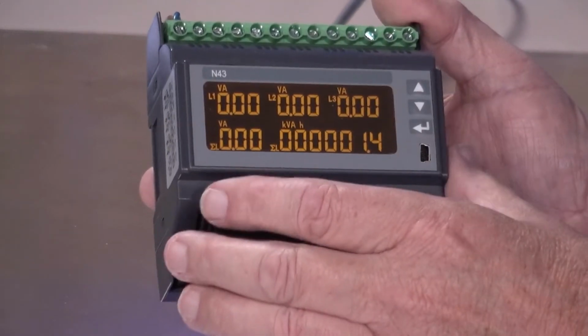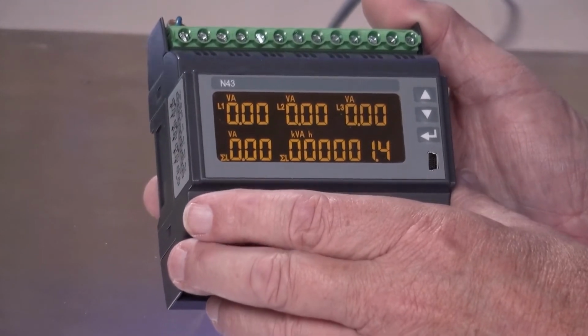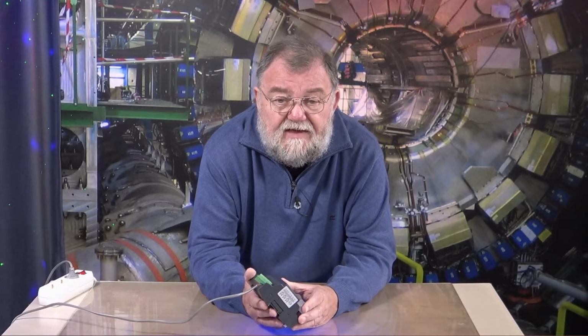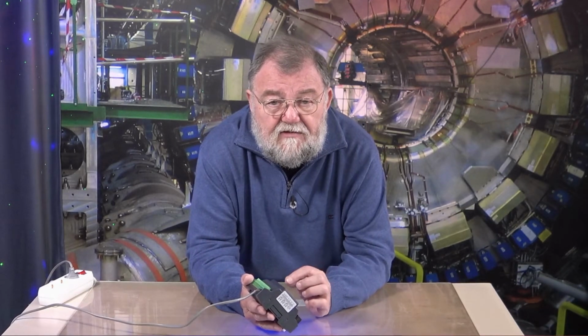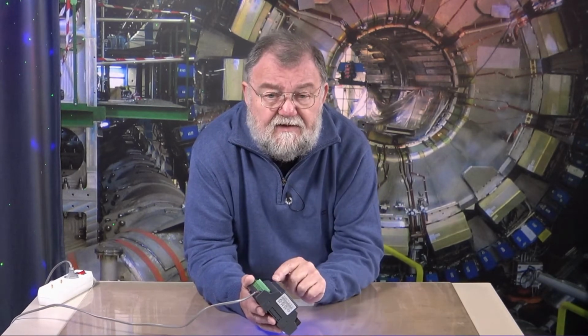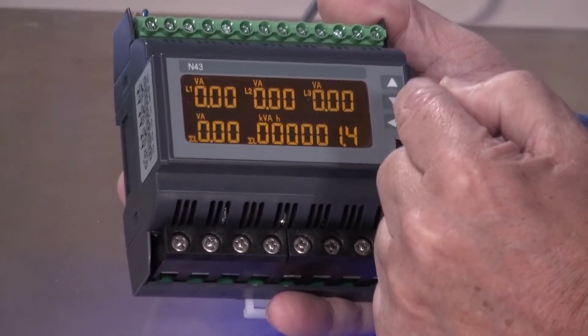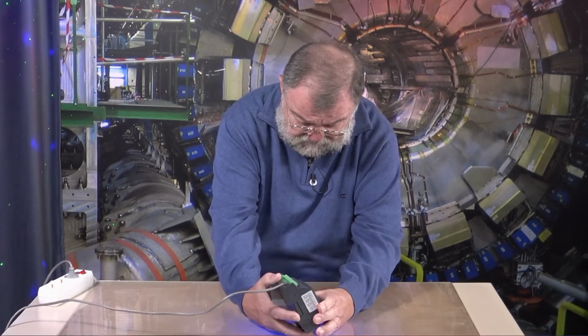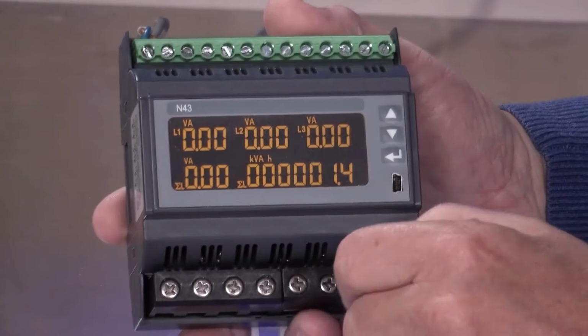What we also have here is an impulse output for the working power, meaning I can attach a counter externally over 2 lines and let the counter show me something like an electricity clock, because it gives an impulse out. The device does this too, cumulative for all 3 phases, and it would have a display far away for the power consumption - as you can see, the display is lit up. It also has an RS485 interface and can be built into a Modbus system, into a more complicated process control.